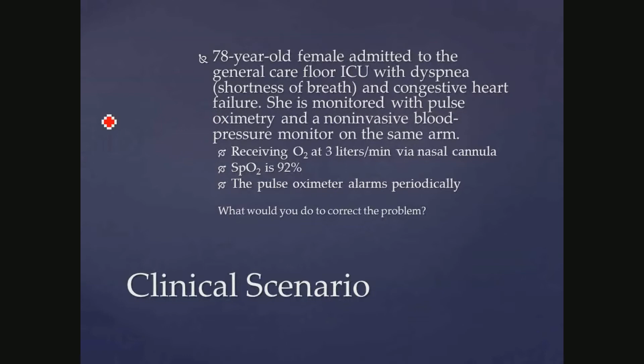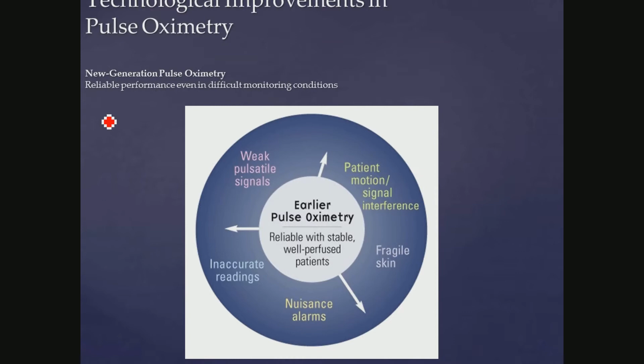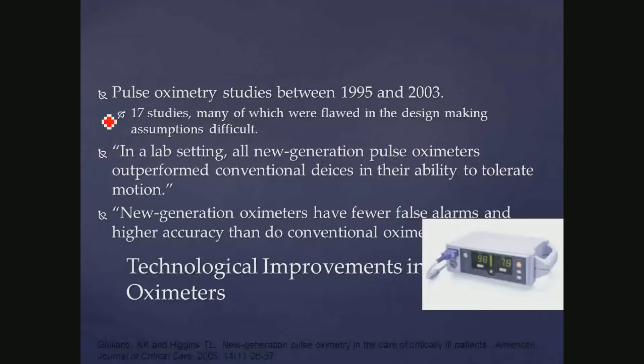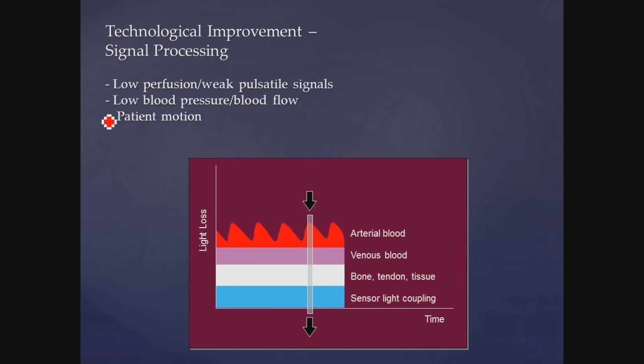Some improvements that we've made as time has gone on. Earlier, the first portion of using pulse oximeter, we were using it in the OR. We had stable, relatively motionless, well-perfused patients. As we got outside into the general care floor, you end up with all kinds of other problems, and that's where the new generation pulse oximetry has tried to improve it. All new generation pulse oximeters, regardless of manufacturer, work better than the older generation ones. So you're seeing fewer false alarms in the presence of reduced blood flow from low pulsatile signals, as well as through patient motion, because that motion will give you difficulty in finding where the arterial signal is.